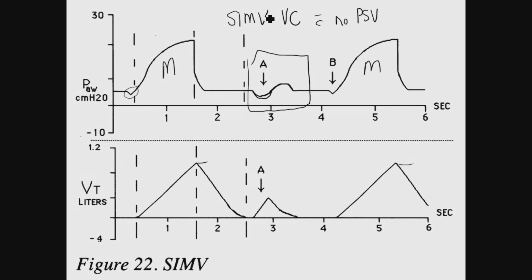But I thought you said if the ventilator notices that they're trying to take a breath, it counts that as part of the cycle. That would be a mandatory breath. That would be one of these two. It noticed that the patient had a trigger, and it was time for a mandatory breath, so it gave a mandatory breath. If it's not time for a mandatory breath, it just allows a spontaneous breath to happen. It allows those spontaneous breaths to occur interspersed between the mandatory breaths.